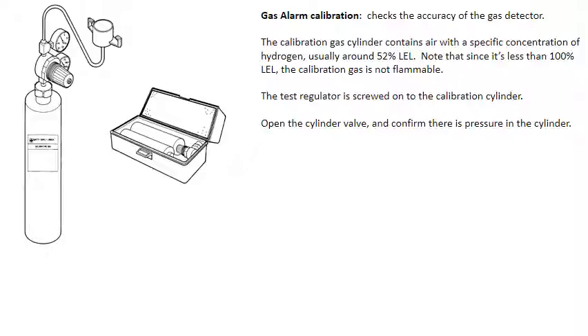The calibration gas cylinder contains air with a specific concentration of hydrogen, usually around 52% of the lower explosive limit. Note that since it's less than 100% LEL, the calibration gas is not flammable. The test regulator is screwed onto the calibration cylinder. Open the cylinder valve and listen to confirm that there is pressure in the cylinder.